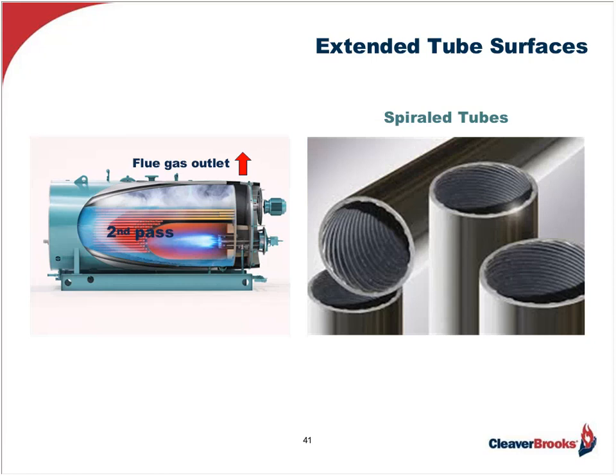In both the Elite and the Premium packages, the optimized tubes are actually spiraled tubes, and as mentioned earlier, are used to increase convective heat transfer. By this I mean the tubes are specially designed to include a particular number of ribs per inch. The ribs are also machined at a specific angle with a specific height and width to provide the maximum contact area, while breaking up the laminar flow of the gases as they travel through the second pass before exiting the stack.